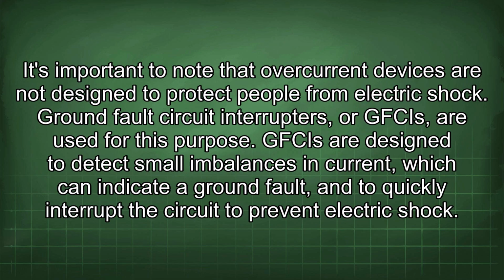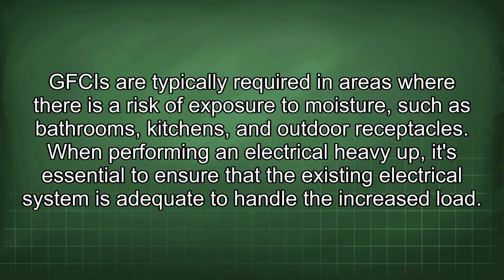It's important to note that overcurrent devices are not designed to protect people from electric shock. Ground fault circuit interrupters, or GFCIs, are used for this purpose. GFCIs are designed to detect small imbalances in current, which can indicate a ground fault, and to quickly interrupt the circuit to prevent electric shock. GFCIs are typically required in areas where there is a risk of exposure to moisture, such as bathrooms, kitchens, and outdoor receptacles.